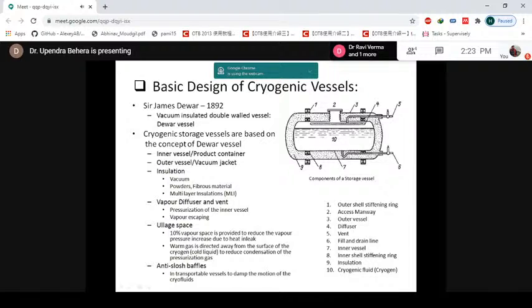Also, when you use warm gas for pressurizing, this warm gas does not directly hit the top surface of the cryogen - it is distributed. The warm gas is directed away from the surface. If you can see, the hole is at the top, not at the bottom, so it comes indirectly and pressurizes the liquid. This reduces the condensation of the pressurization gas.